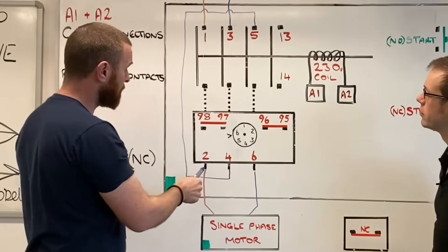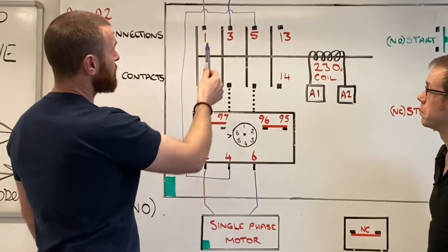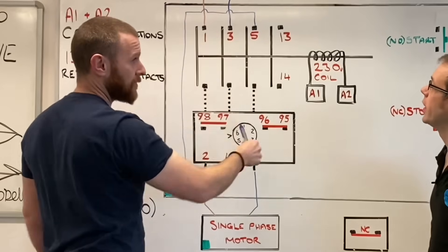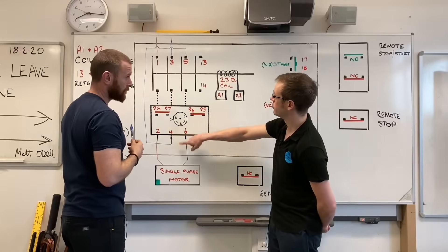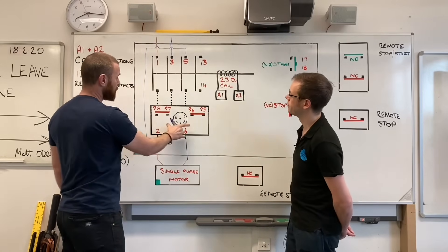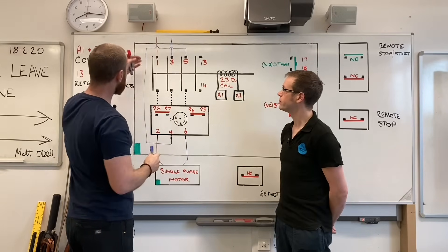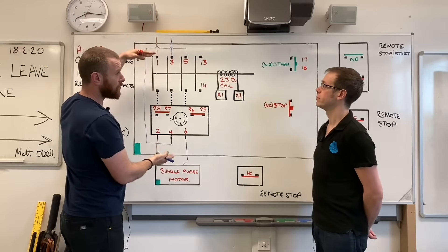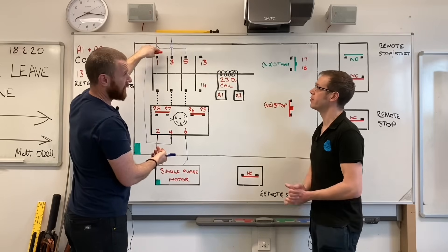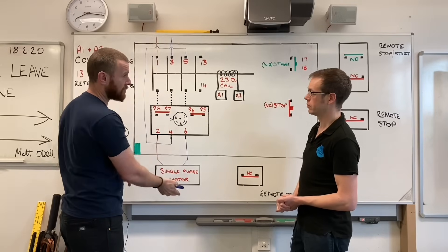So it doesn't actually matter whether you did this, you did it with the line conductor or the neutral. I just think it's better to do the neutral and you've got less, shall we say live wires floating around in the box. So it's better to take the neutral back around and use that again and pass that through the contactor twice. Yes. I think so. So that way the overload relays internally are all being utilized. That's clever. I like that. Okay, so that's the basic. That's basically when you put a DOL starter in, that is exactly what you'll, generally that's all you have to do. Those are the connections you'll make. Yeah, you just connect if it's single phase or three phase, however you do it, you just connect them in and connect them out and that's it. Smart.